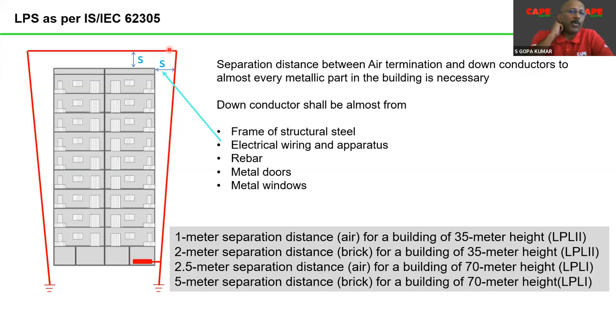Now, this is what is explained in the 62305. Once we explain this subject to the construction site or to the clients, most of the clients say that, no, this is not required, you leave it. We don't want to calculate the separation distance or we don't want to consider separation distance. Please note that if you don't consider separation distance, your lightning protection system is inefficient. Lightning may hit the air termination, but instead of the current flowing through the down conductor, there will be flashover between the air termination and the metallic parts of the building. As a result, current is going to flow through your building, which may destroy so many things.